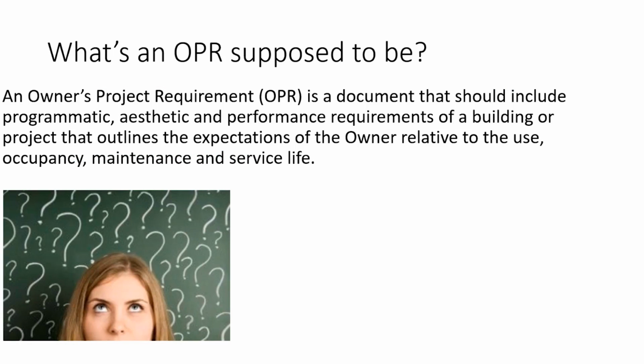So a lot of people always wonder what an OPR is supposed to be. It's often thought of as something solely related to commissioning, or that document you just need to meet a LEED requirement. It should include all the requirements from programming, aesthetics, and performance of a building through its service life. A lot of these are always forgotten. Sometimes they're just copied and pasted from project to project without any thought on the huge impact they could have from the design or life cycle of a project. A lot of the time they're even just put together at the end of design to match the design, just to meet a LEED submission.